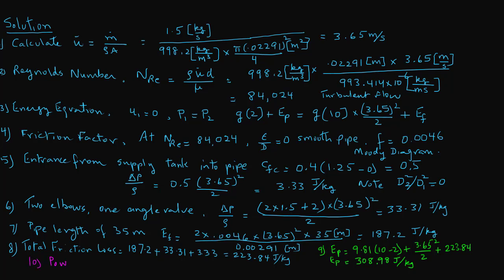In step 10, to obtain the pump power, we multiply the energy term by the mass flow rate: Power = 308.98 J/kg × 1.5 kg/s = 463.5 joules per second. Since joules per second equals watts, the power requirement of the pump is 463.5 watts.